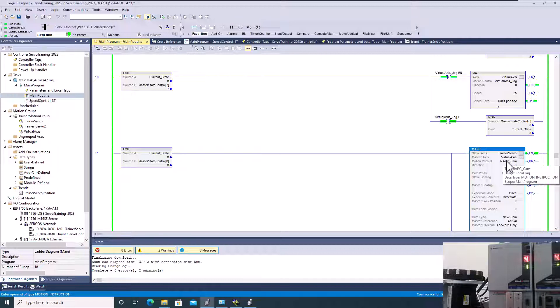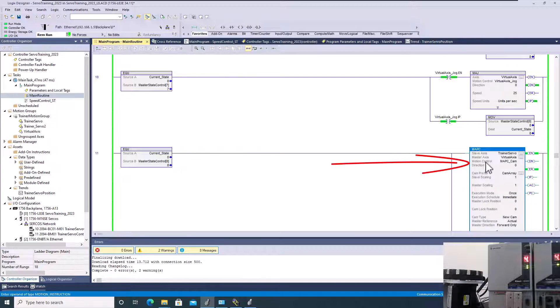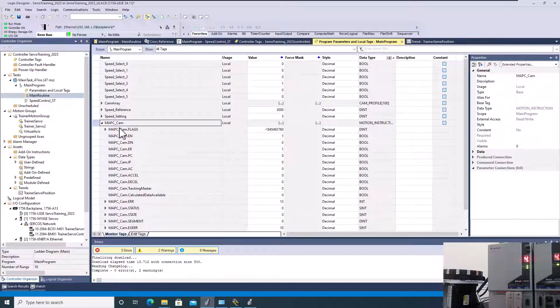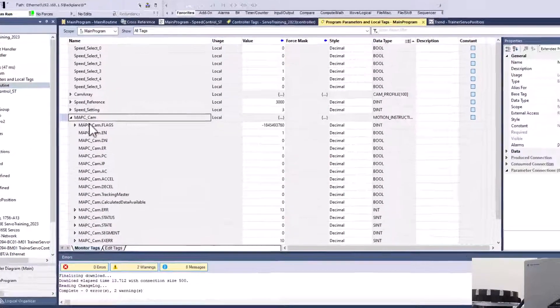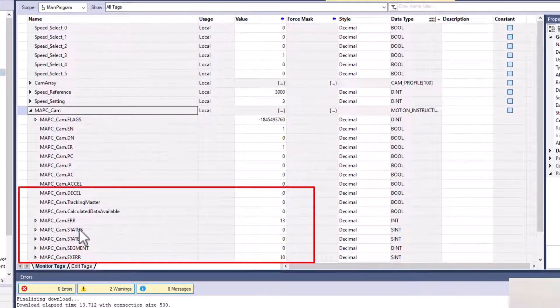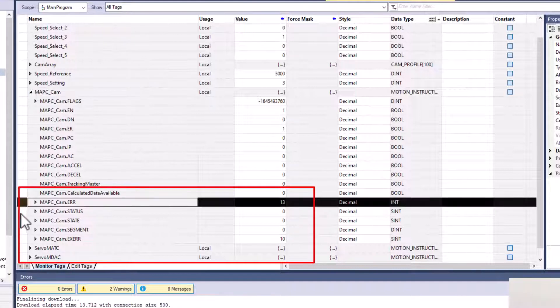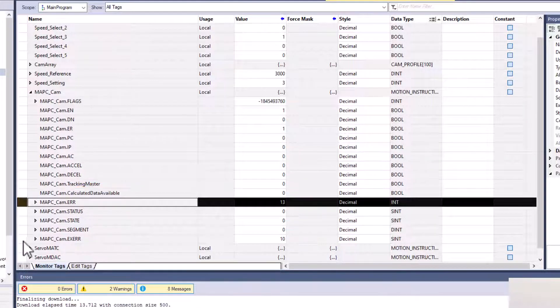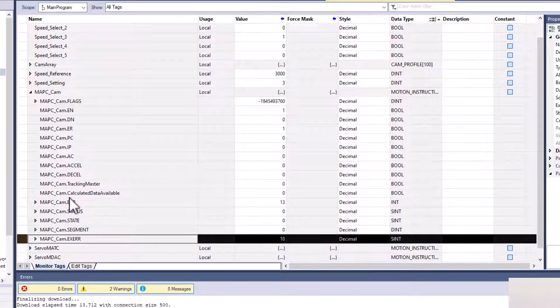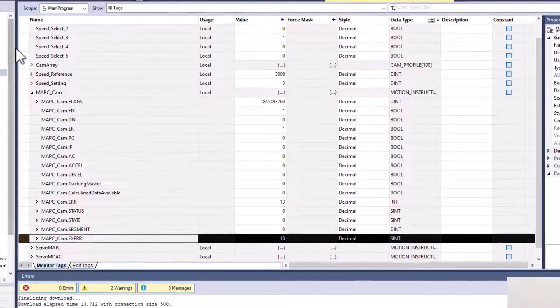So how I found my error, again, you want to go to your tag. So the motion control, this is your tag. That's the tag I named it. I'm going to go to monitor. And monitor, I'm going to come down here and see what my error code was. My error code was 13 and my extended error is 10. So other than logging into Rockwell and their knowledge base and digging down and spending hours trying to find the problem, what I'm trying to do is show you how to easily fix this.